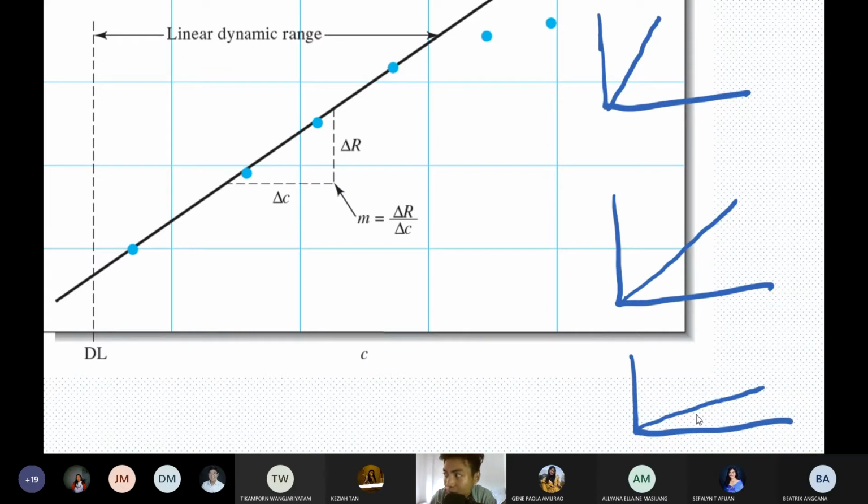You may want to check whether there are issues with the light source, or issues with the injector. So whenever you see a slope like this, that means you have to check your instrument if it's working well or not. The acceptable curves are this one, the most sensitive one, and this normal curve here. This one, not much.